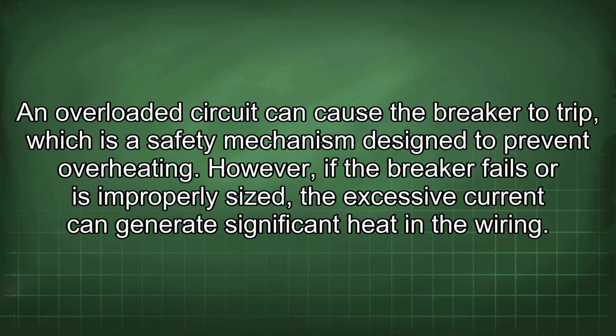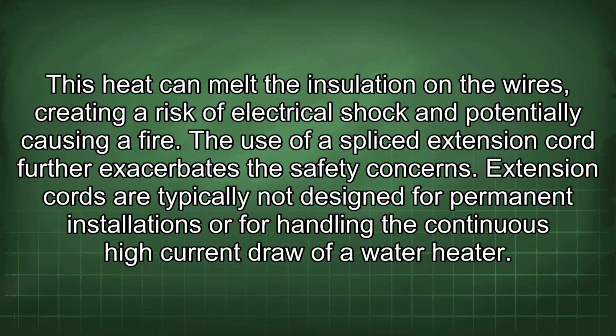An overloaded circuit can cause the breaker to trip, which is a safety mechanism designed to prevent overheating. However, if the breaker fails or is improperly sized, the excessive current can generate significant heat in the wiring. This heat can melt the insulation on the wires, creating a risk of electrical shock and potentially causing a fire.